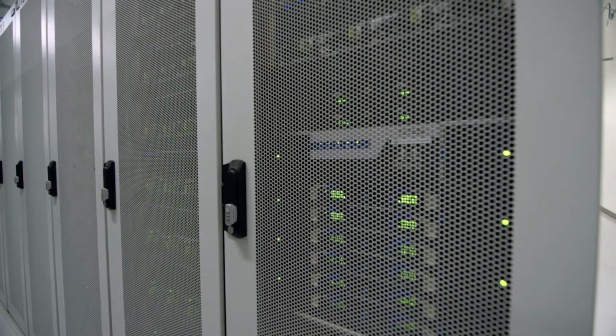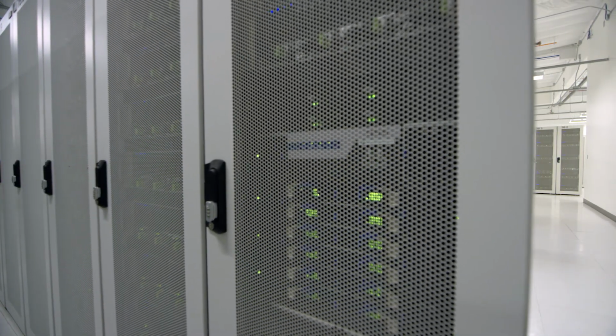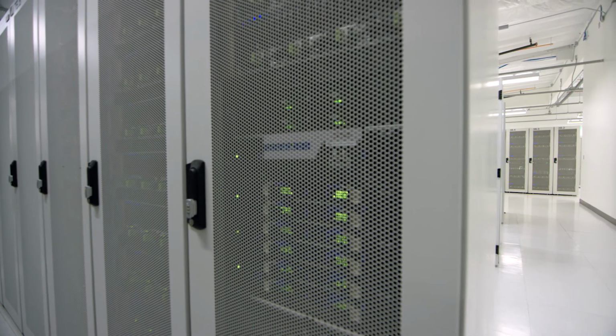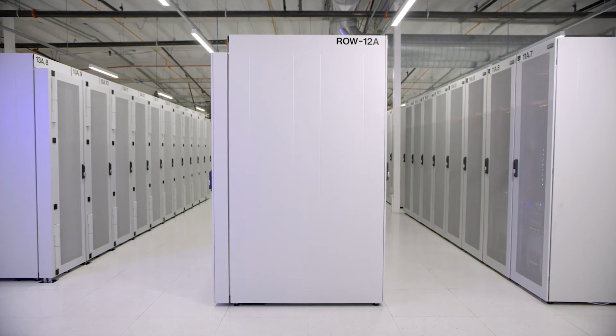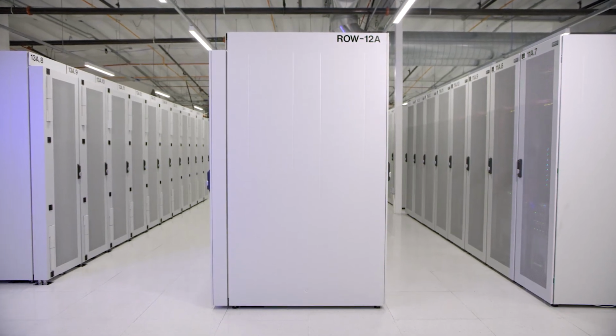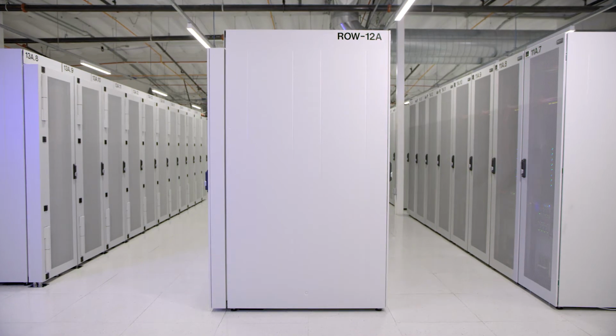And that is just a rule of thumb which allows you beforehand, before you even start racking, to understand whether what you ordered is actually what you got, firstly. And secondly, it allows you to start to plan the deployment in a way that allows you to have that type of airflow. Airflow has always been important in terms of data centers. It helps with cooling in almost any environment, but in our particular environment, the new normal is going to be airflow consistently from the front of the cabinet to the back through the doors.